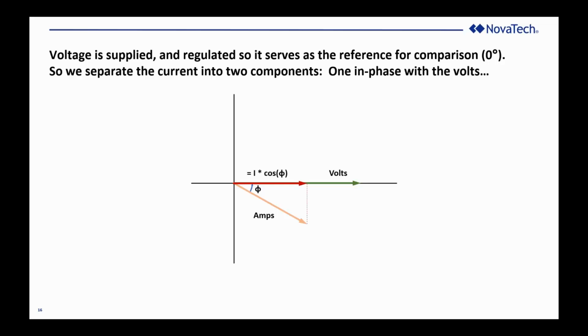Now that's straight out of the time domain. That phase angle that we're talking about is the delta t between the time that the voltage sine wave crosses going up, let's say, from the 0 point, to the time when the current crosses the axis going up. So that phi is really just milliseconds or microseconds translated into degrees, where one 360-degree wavelength is 16 2/3 milliseconds if you're working at 60 hertz, or 20 milliseconds if you're working at 50 hertz.